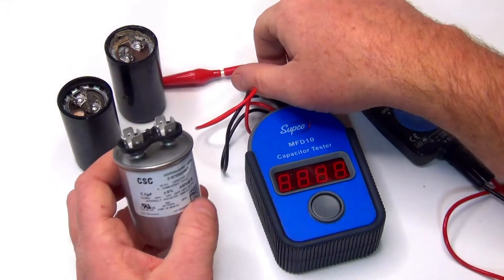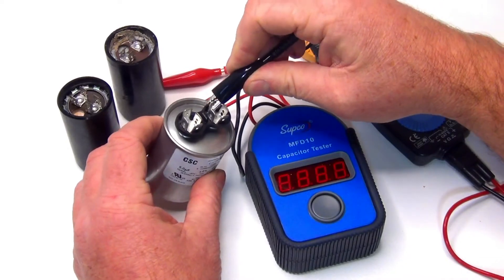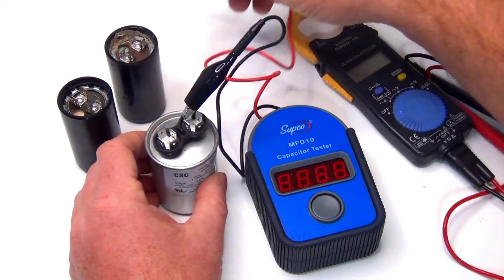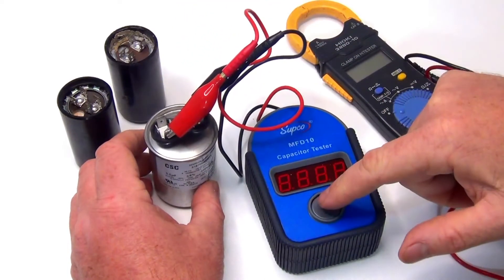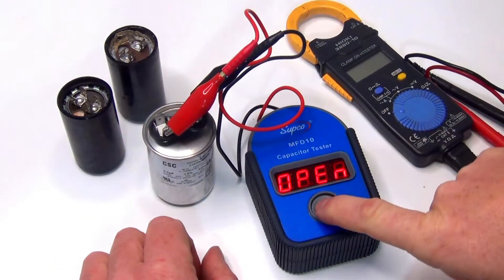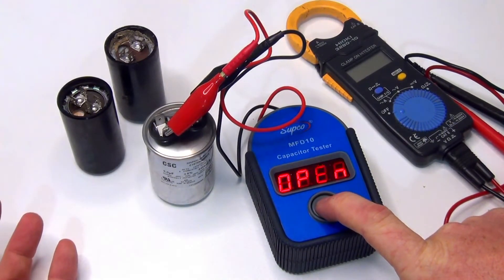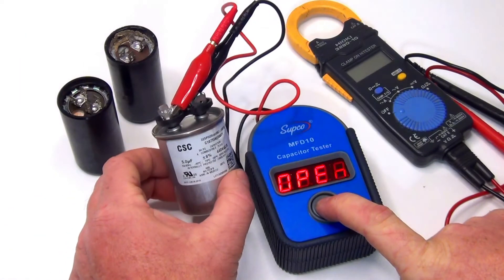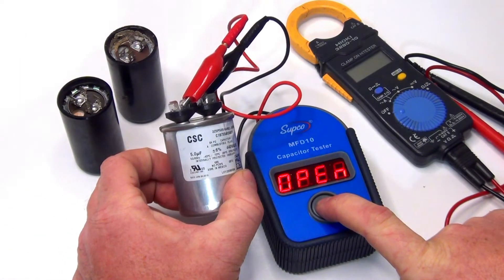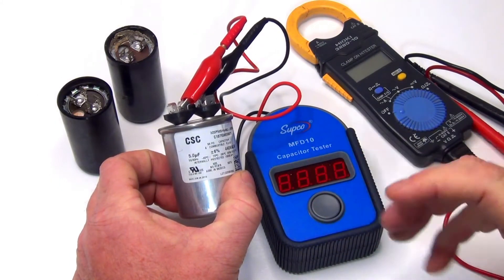We're going to test this one first. It doesn't matter what lead goes where — black, red, whatever. For this particular one, we just hold it down and it shows open. If it says open or shorted, that's a bad capacitor. It should show a number and then we can compare that number to the rating on the side. Here it's a 5 UF capacitor, so if we pushed it and got a 1, we know it's failing.